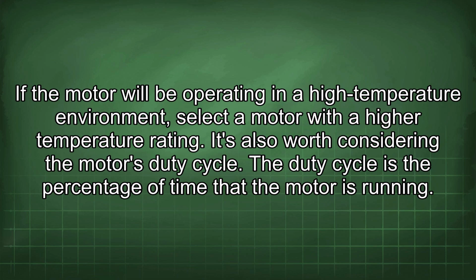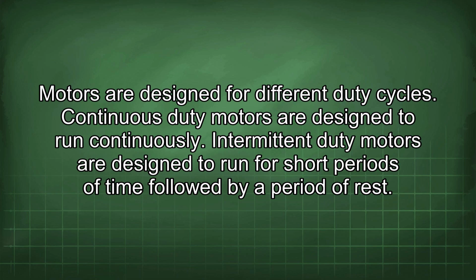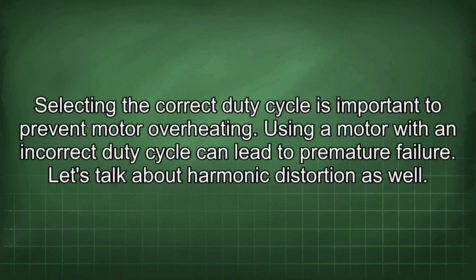It's also worth considering the motor's duty cycle. The duty cycle is the percentage of time that the motor is running. Motors are designed for different duty cycles. Continuous duty motors are designed to run continuously. Intermittent duty motors are designed to run for short periods of time followed by a period of rest. Selecting the correct duty cycle is important to prevent motor overheating. Using a motor with an incorrect duty cycle can lead to premature failure.